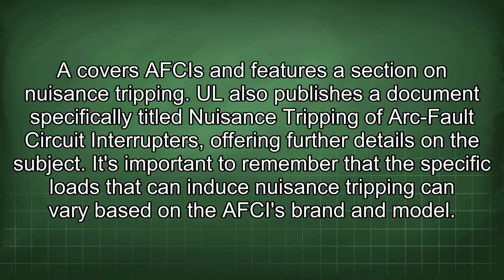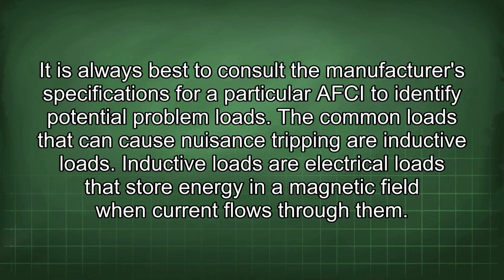It's important to remember that the specific loads that can induce nuisance tripping can vary based on the AFCI's brand and model. It is always best to consult the manufacturer's specifications for a particular AFCI to identify potential problem loads.